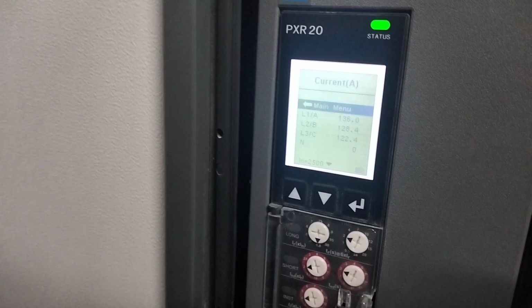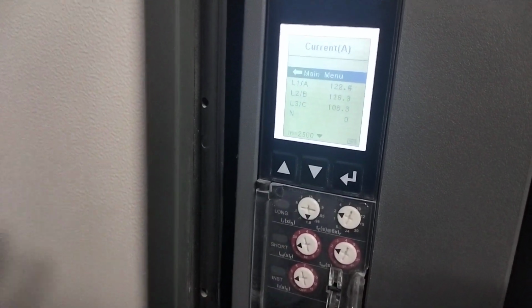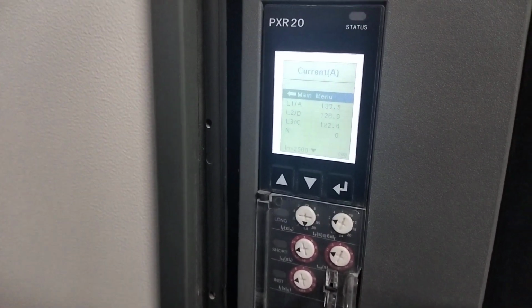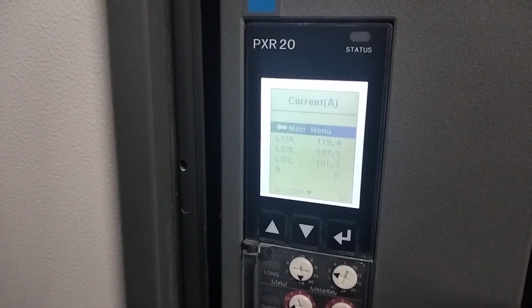Okay. Right now it's 136, either line 1 or line 2. The display will come only if the ampere is above 100 ampere. If it is less than 100, it won't show, okay, because it's self-powered.